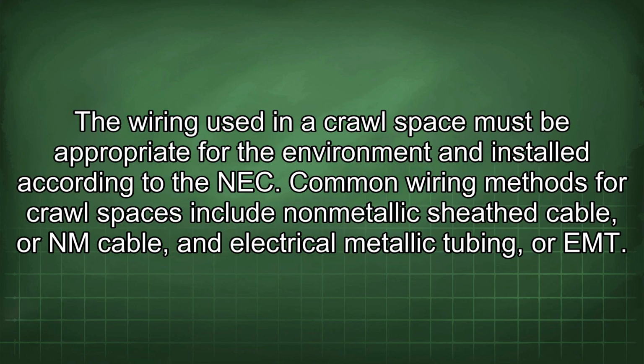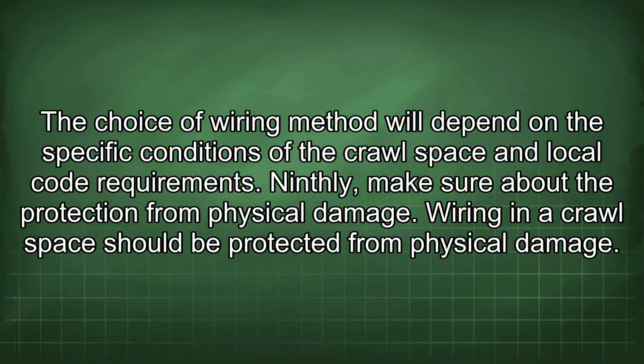Eighthly, let us talk about the wiring method. The wiring used in a crawl space must be appropriate for the environment and installed according to the NEC. Common wiring methods for crawl spaces include non-metallic sheathed cable, or NM cable, and electrical metallic tubing, or EMT. The choice of wiring method will depend on the specific conditions of the crawl space and local code requirements.